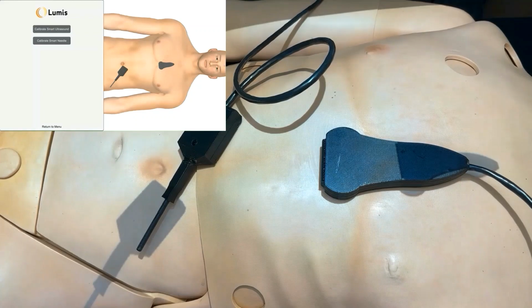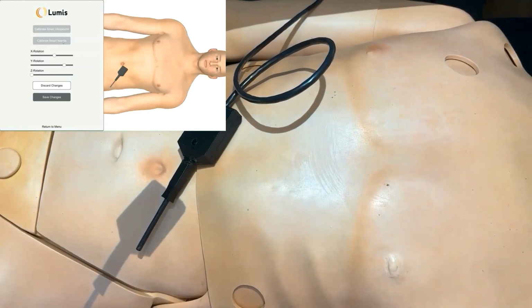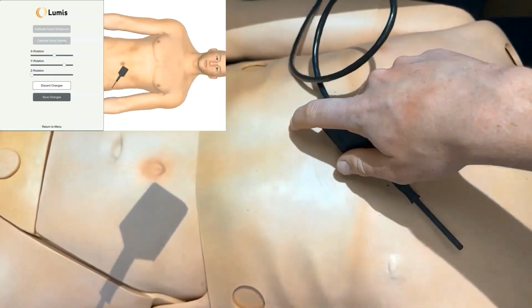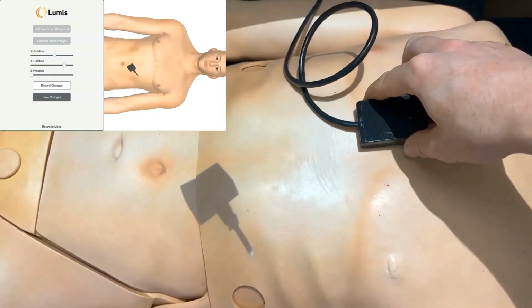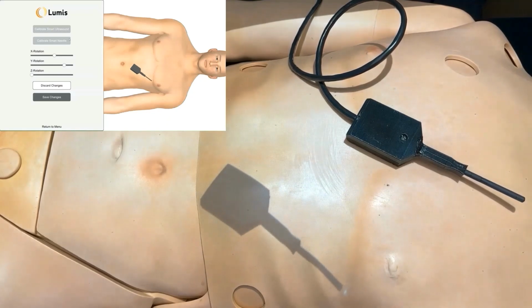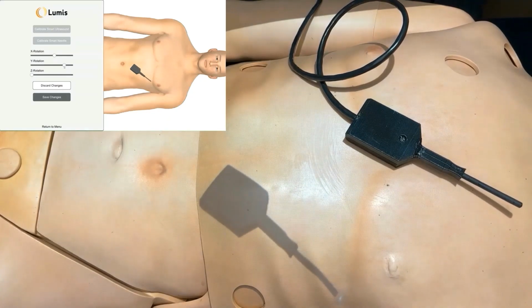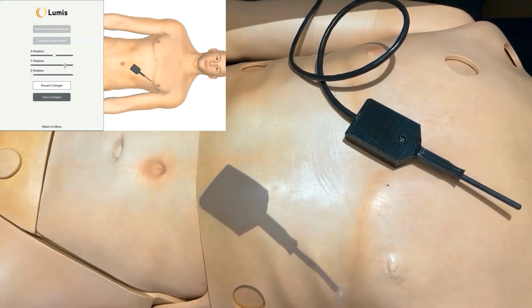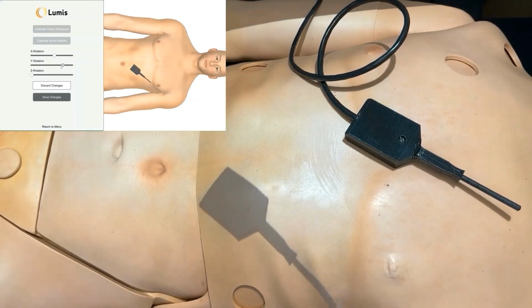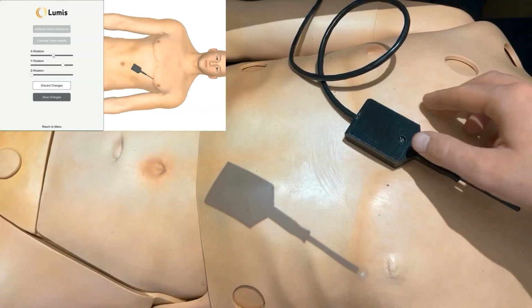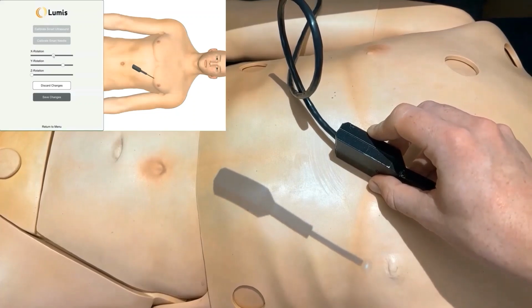To calibrate the Smart Needle, press the Calibrate Smart Needle button on the tablet. This will temporarily remove the virtual probe from the body to limit distractions. You can adjust the sliders on the tablet screen to alter the X, Y, and Z axis rotations of the virtual needle. Do this until the orientation of the virtual needle is identical to that of the Smart Needle. It is useful to move the Smart Needle in a variety of different positions to ensure that this calibration is robust.